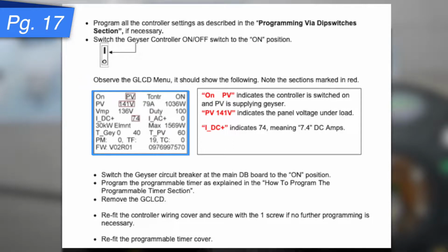On PV. Remember before? It was AC. This is now PV, all right. That indicates the controller is switched on, and the solar, the PV, is now supplying the geyser. You should still be getting panel voltage, PV 141 volts, but now you should be getting some amps coming through. The IDC plus must indicate something. In this case, I've got 74, and that's not 74 DC amps, that's 7.4 DC amps.